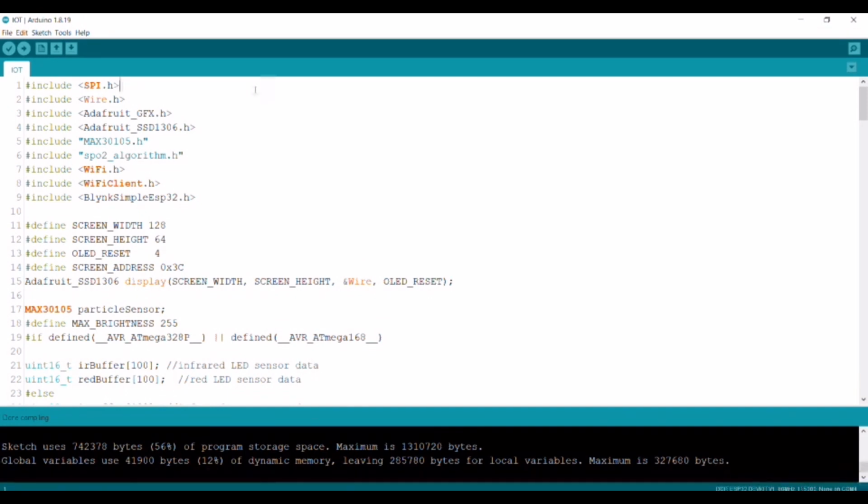As you continue to shine the light and take the photodetector readings, you quickly start to get a heartbeat pulse reading. The second part is pulse oximetry, based on the principle that the amount of red and infrared light absorbed varies depending on the amount of oxygen in your blood. The oxygenated blood absorbs more infrared light, while the deoxygenated blood absorbs more red light. By measuring the ratio of infrared light and red light received by the photodetector, the oxygen level in the blood is calculated.